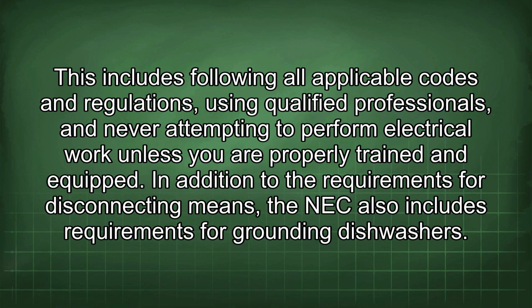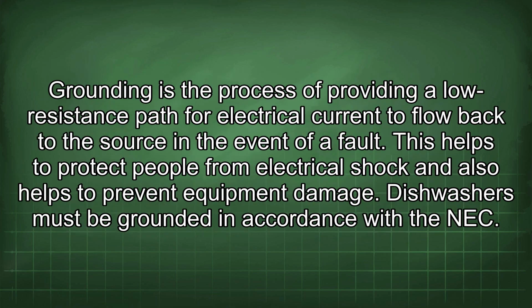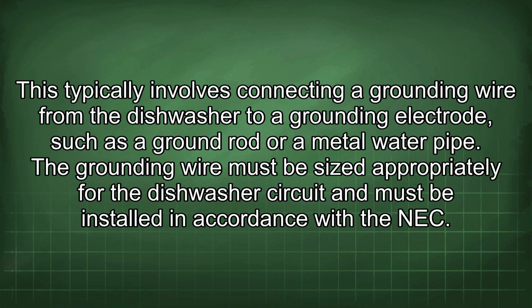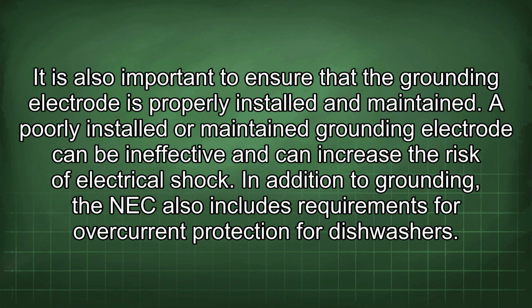In addition to the requirements for disconnecting means, the NEC also includes requirements for grounding dishwashers. Grounding is the process of providing a low resistance path for electrical current to flow back to the source in the event of a fault. This helps to protect people from electrical shock and also helps to prevent equipment damage. Dishwashers must be grounded in accordance with the NEC. This typically involves connecting a grounding wire from the dishwasher to a grounding electrode, such as a ground rod or a metal water pipe. The grounding wire must be sized appropriately for the dishwasher circuit and must be installed in accordance with the NEC. It is also important to ensure that the grounding electrode is properly installed and maintained. A poorly installed or maintained grounding electrode can be ineffective and can increase the risk of electrical shock.